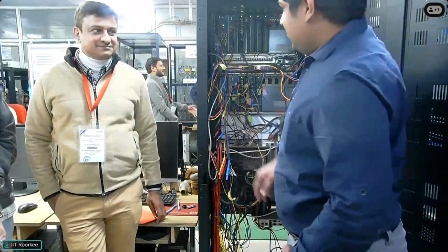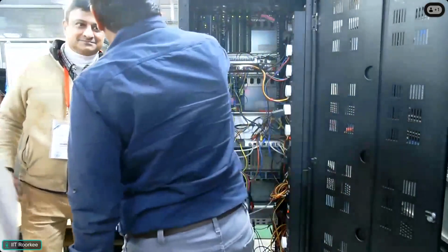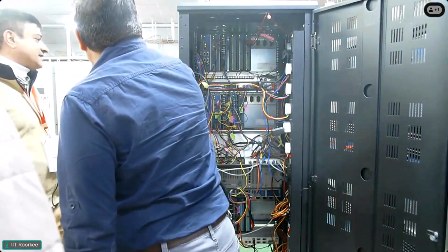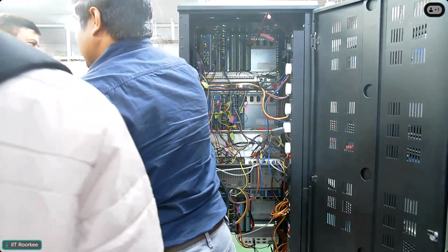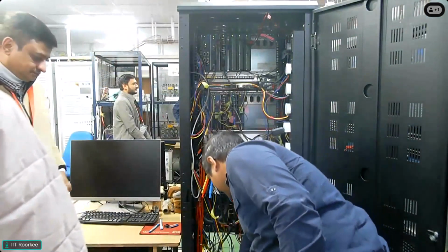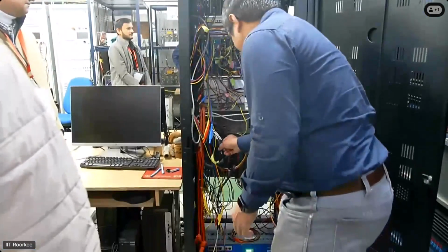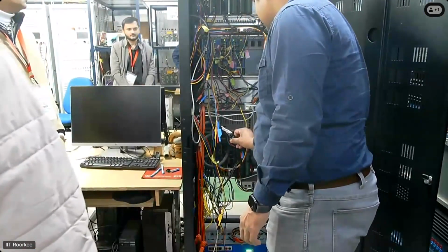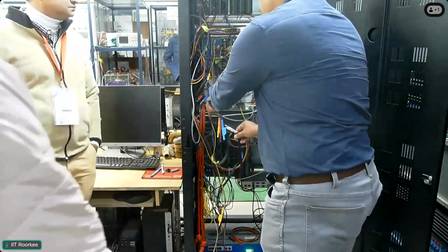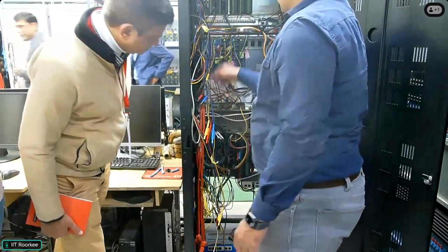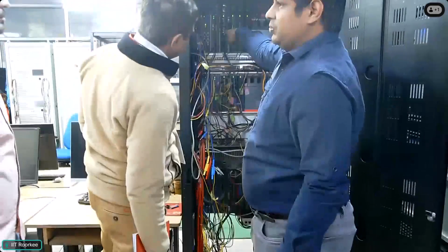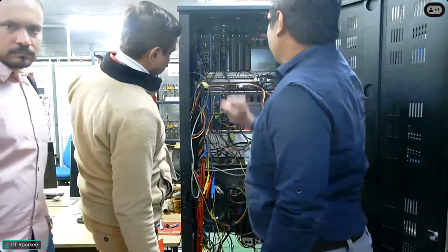Okay, so in this, if you can see, we have come from RTDS through the GTAO card to this amplifier. Then from this amplifier, if you see this cable coming out, it has 3 voltages and neutral, and this is 3 currents and neutral. So from the amplifier we give it here, and these wires are going to the CT module of the PMU. Okay, so here this is the CTPT module.